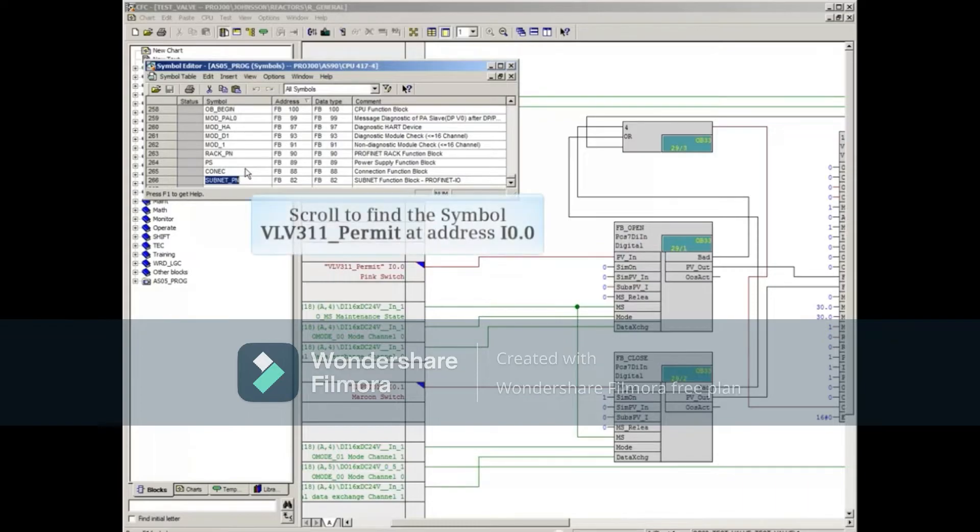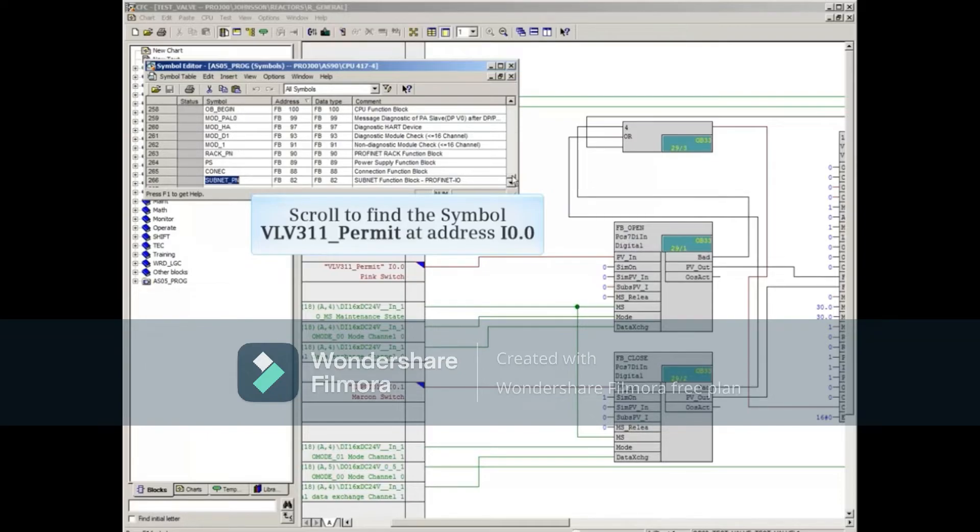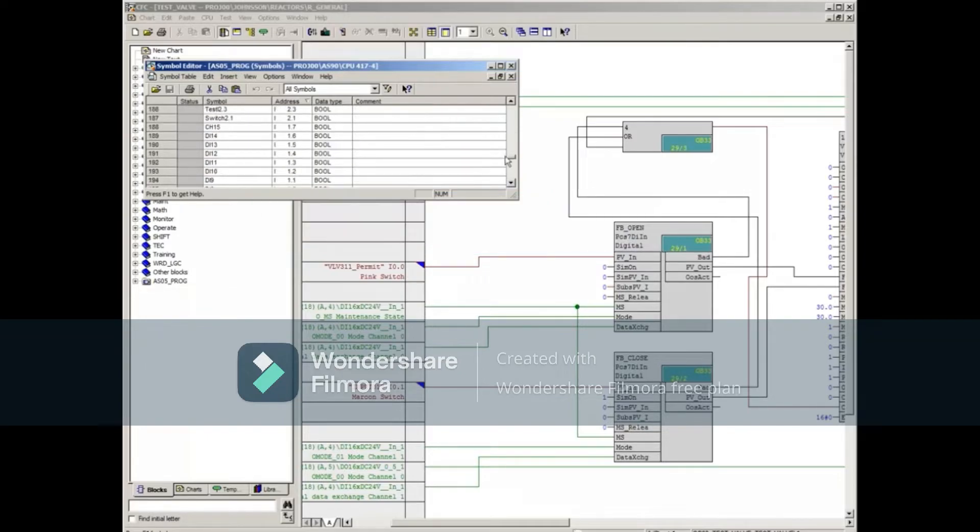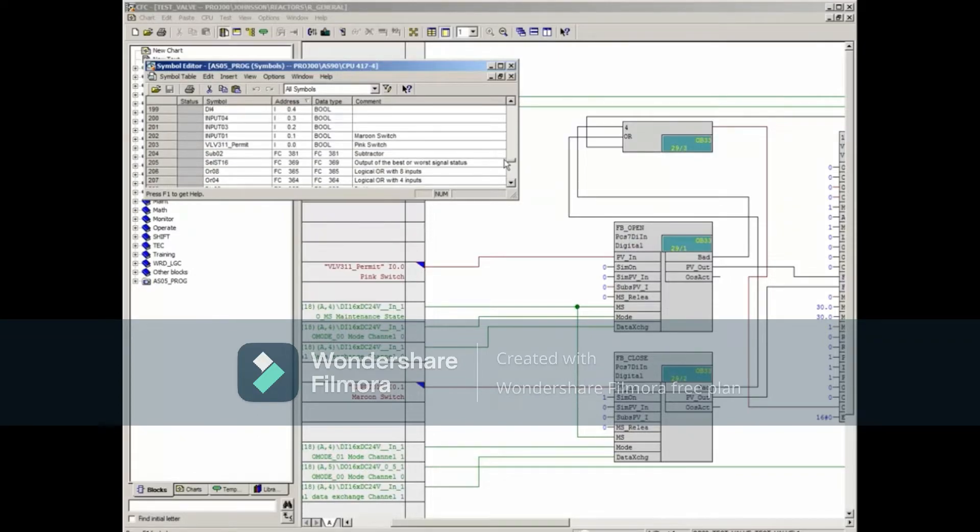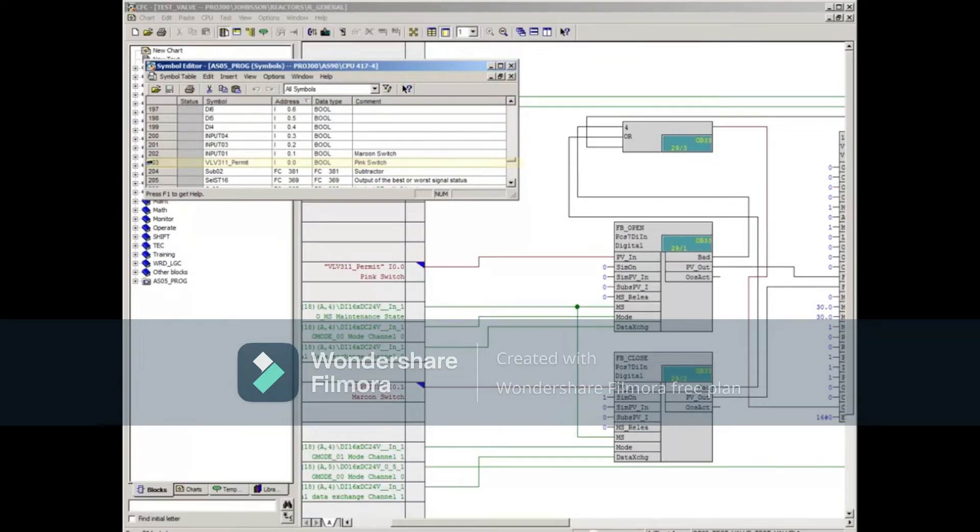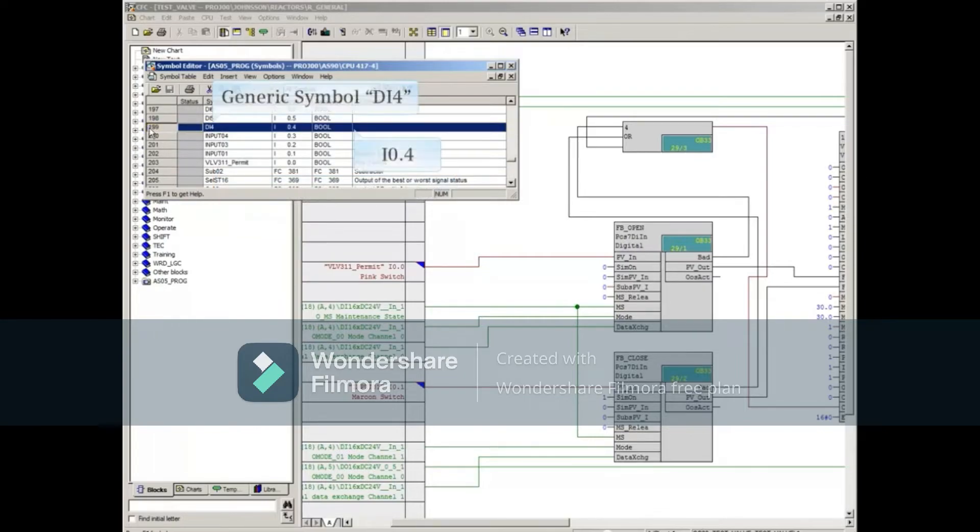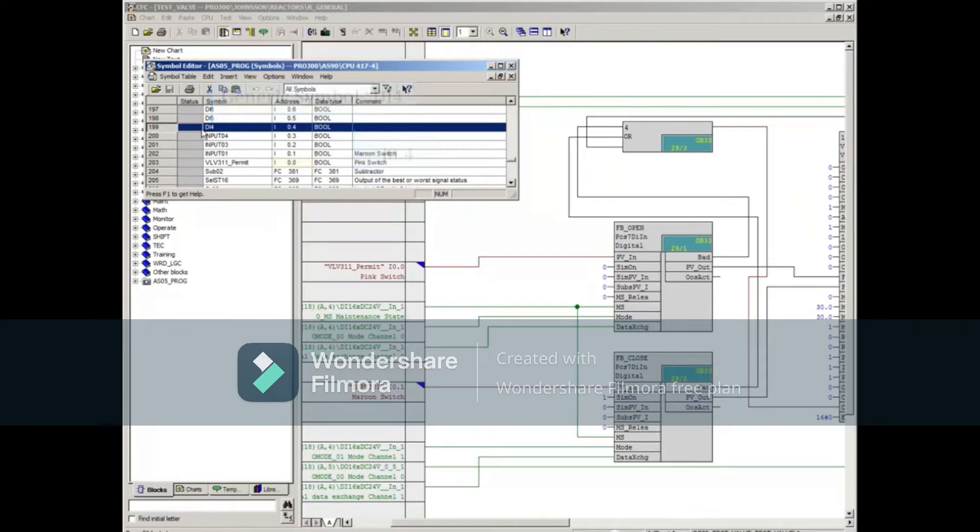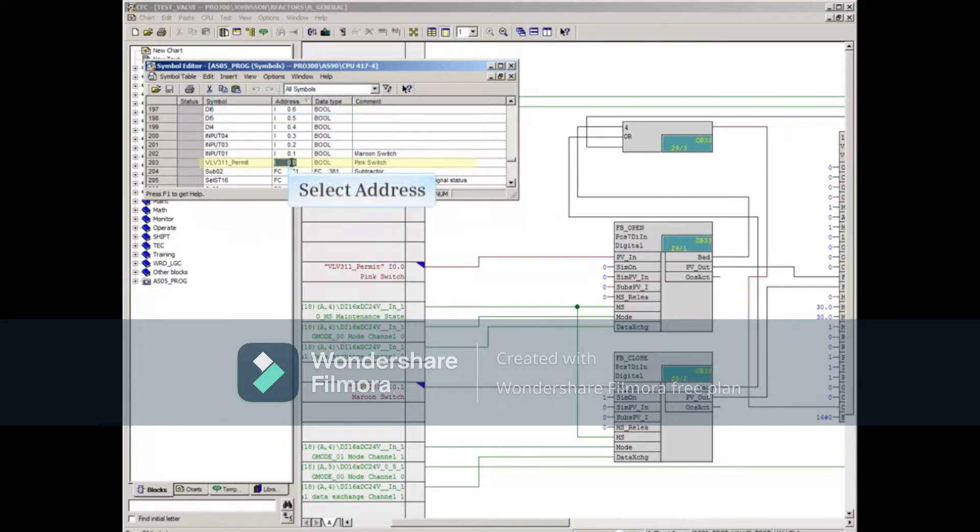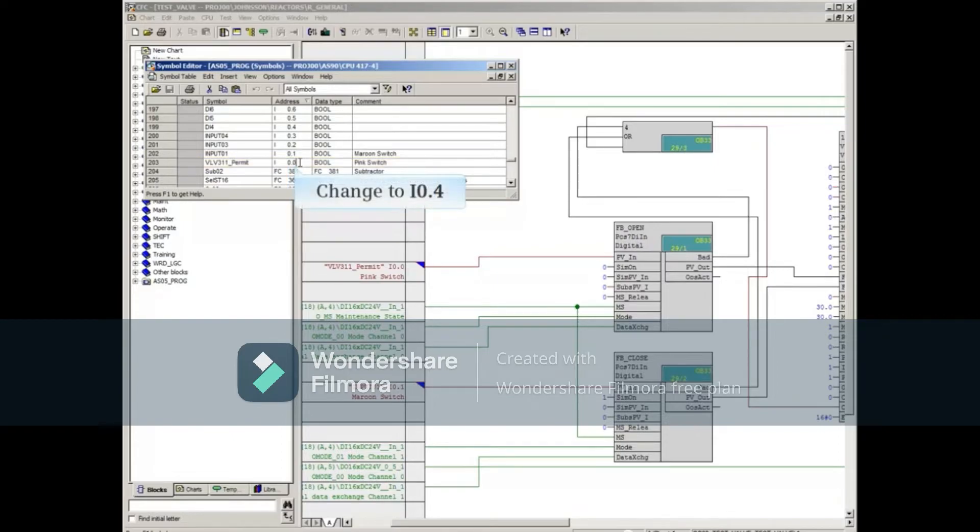Then scroll to find the symbol VLV311_Permit at address input 0.0. The address we're going to move it to is input 0.4, and in this example already has a symbolic name configured. We can now select the Address entry of the symbolic name we want to move, and change it to input 0.4. Then click in a different cell for the change to take effect.